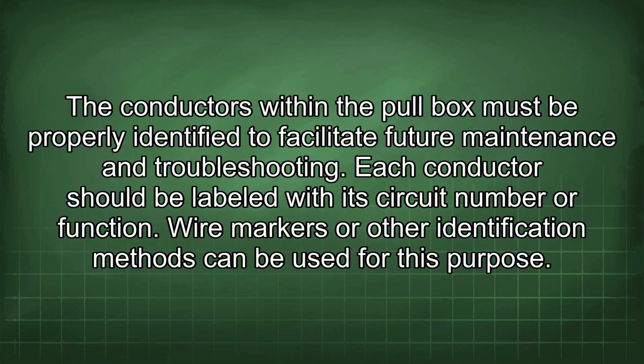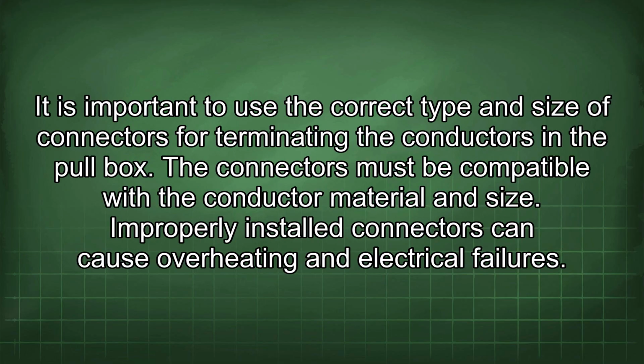The conductors within the pull box must be properly identified to facilitate future maintenance and troubleshooting. Each conductor should be labeled with its circuit number or function. Wire markers or other identification methods can be used for this purpose. It is important to use the correct type and size of connectors for terminating the conductors in the pull box. The connectors must be compatible with the conductor material and size. Improperly installed connectors can cause overheating and electrical failures.